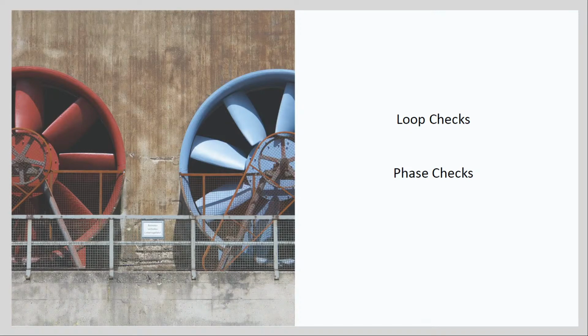So another pre-commissioning check would be AC phase checks. Before three-phase systems are energized, phase checks are completed to verify installation of each electrical phase in the proper order. If three-phase power is installed backwards, called phase rotation, the system may rotate in the wrong direction, but worse, some equipment can't tolerate incorrect sequencing of phases, and you could potentially damage or destroy some of the equipment if it's not wired correctly. So you definitely want to confirm that the phasing is correct.